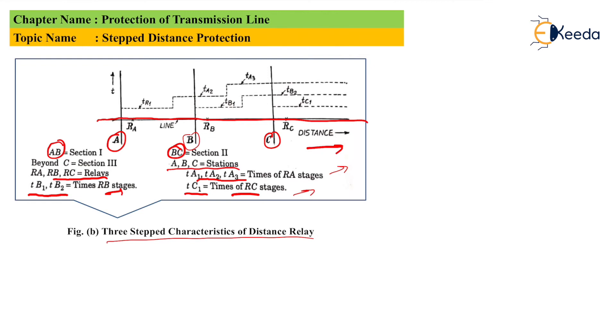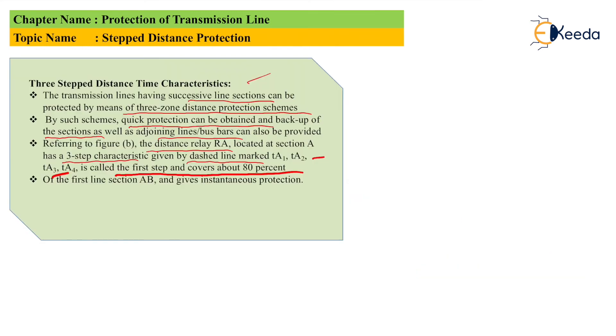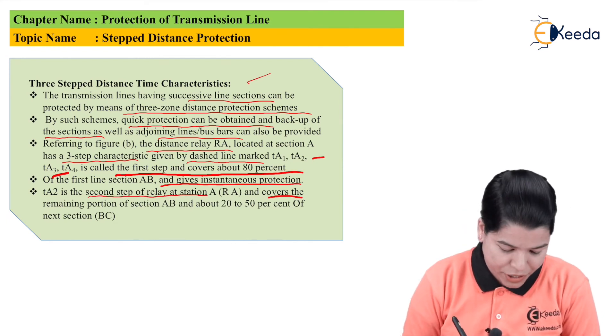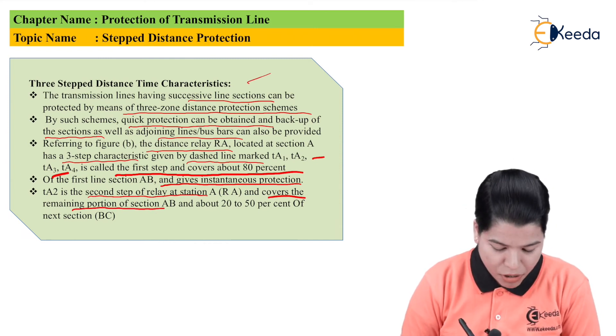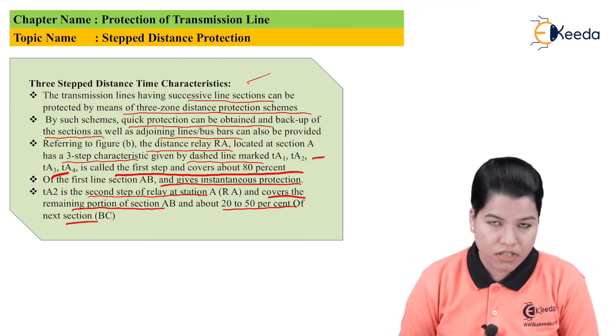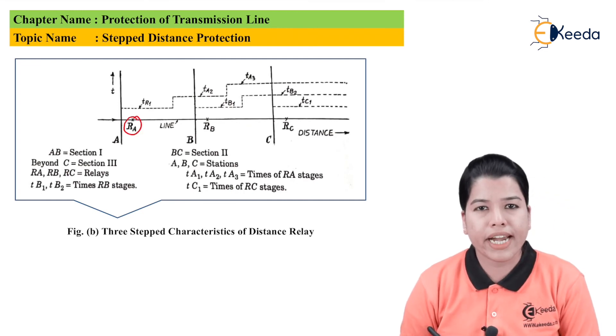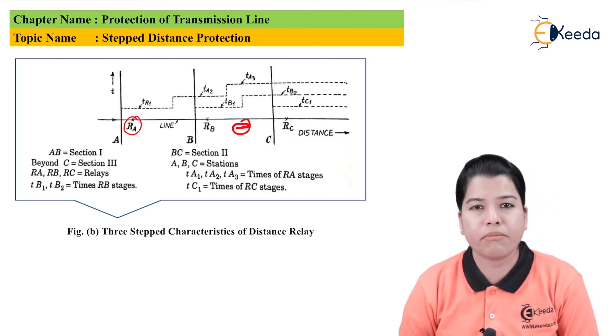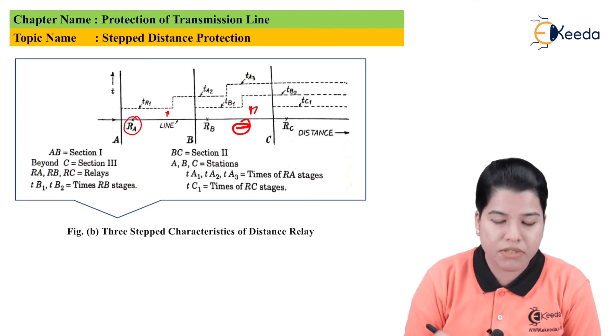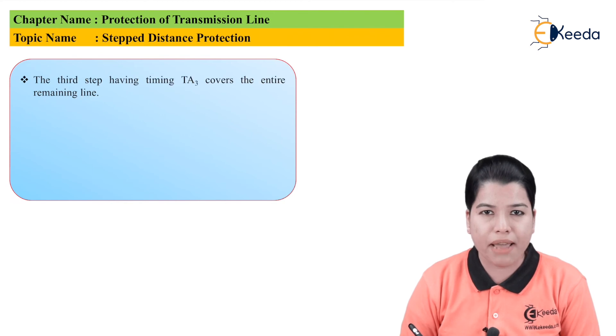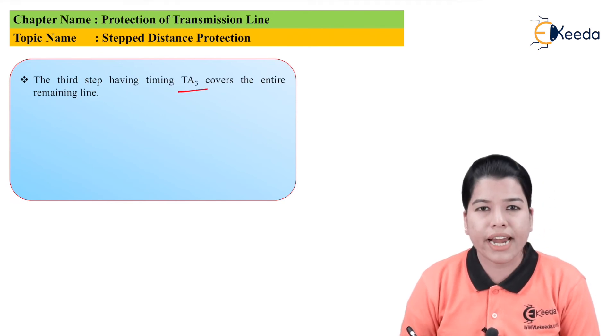For the first section AB, the relay provides instantaneous protection. TA2 is the second step of relay RA and it covers the remaining portion of section AB and about 20% to 50% of section BC. Relay RA protects only 80% of the line, and the remaining portion is protected in the B section. In this way, there is one step for the first section, two steps into the second, and three steps total, so the complete section of the line is protected. The third step has a timing of TA3 and covers the entire remaining line.